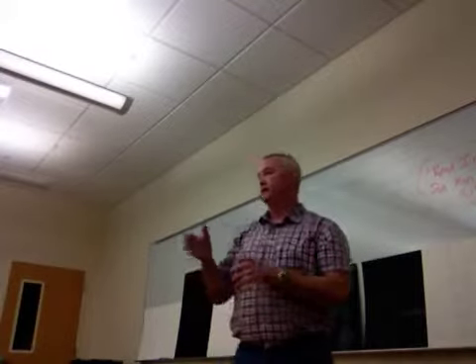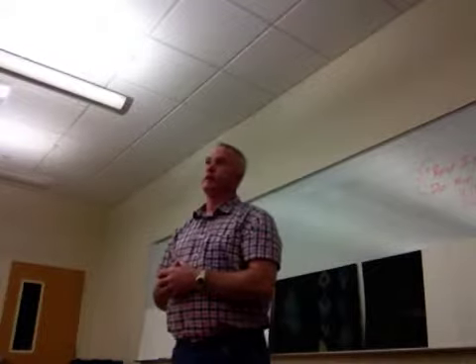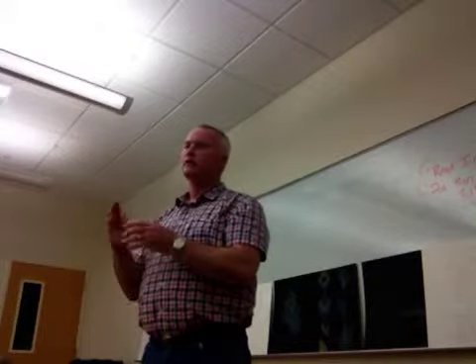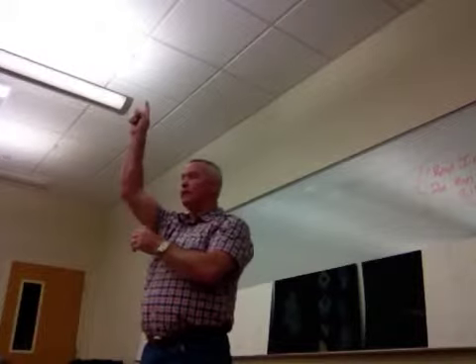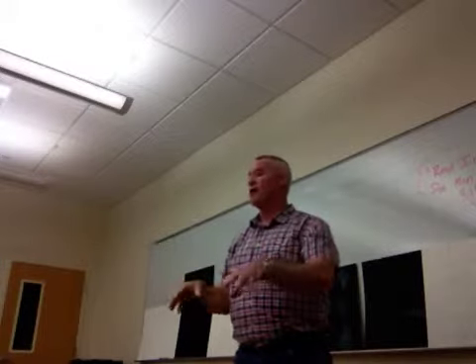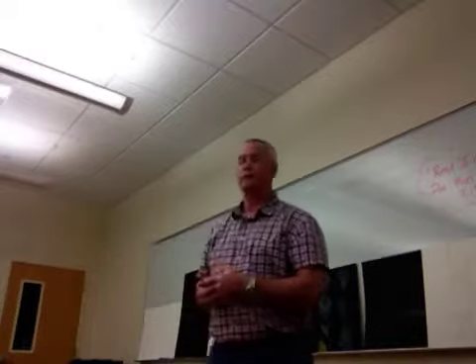When you drain a tub, it won't drain without a vent. It'll sit there and it'll bubble and it'll burble, and it may eventually drain, but the vent is what lets it breathe. So those vents have to go up through a wall or a chase out the roof, and they vent outside, okay? And they're sized according to how many appliances I have on this drain. It could be a 2-inch vent through roof, it could be a 3-inch vent through roof, or 4-inch.